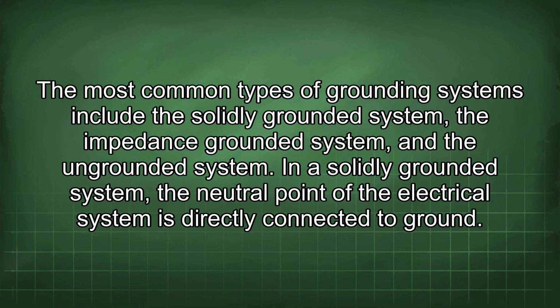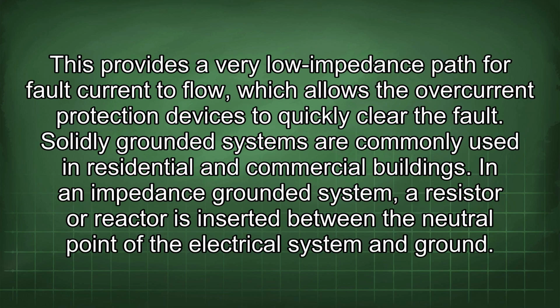The most common types of grounding systems include the solidly grounded system, the impedance grounded system, and the ungrounded system. In a solidly grounded system, the neutral point of the electrical system is directly connected to ground. This provides a very low impedance path for fault current to flow, which allows the overcurrent protection devices to quickly clear the fault. Solidly grounded systems are commonly used in residential and commercial buildings.